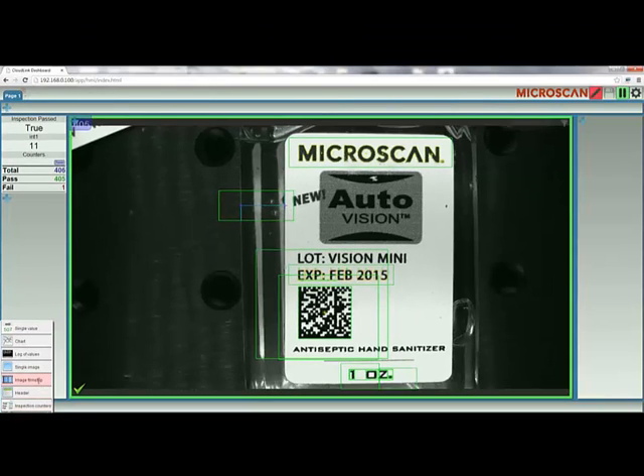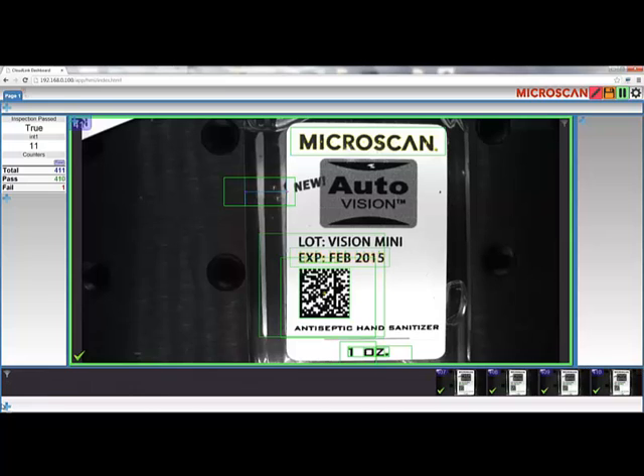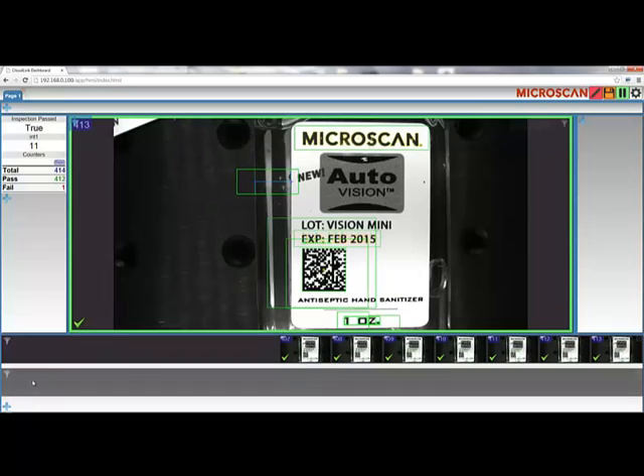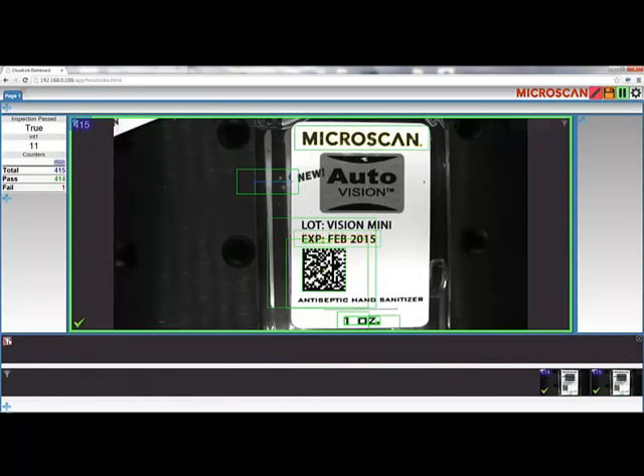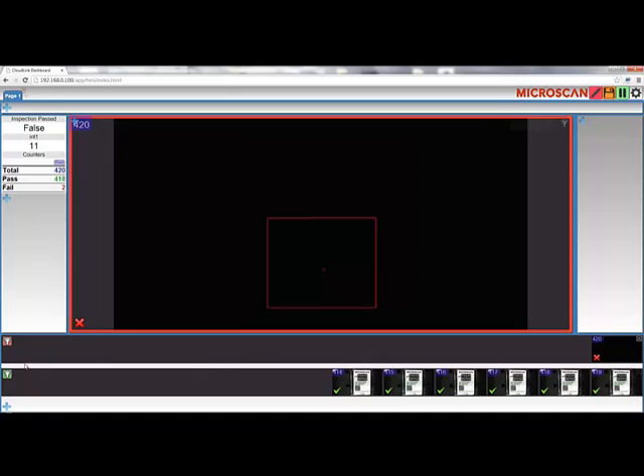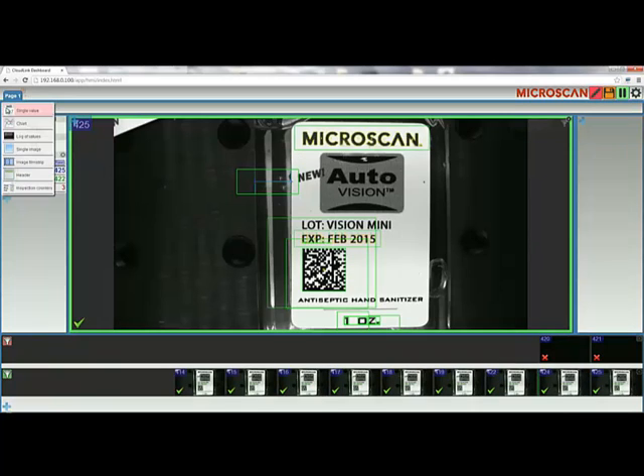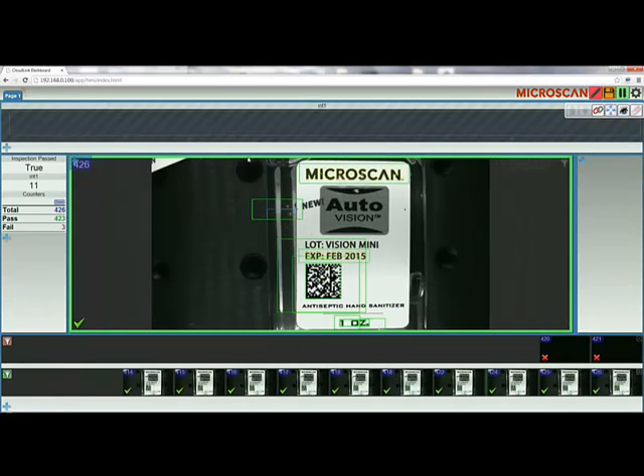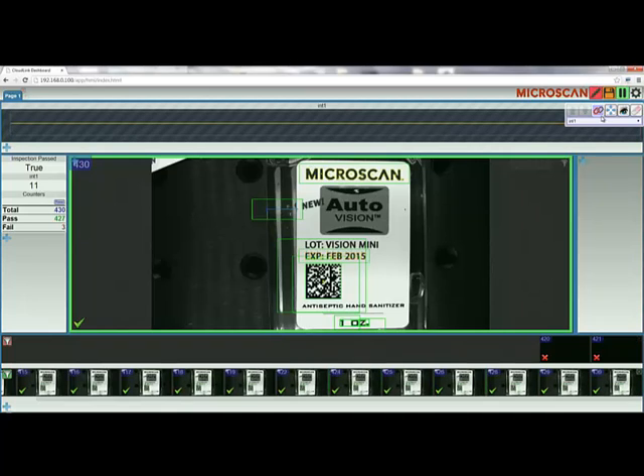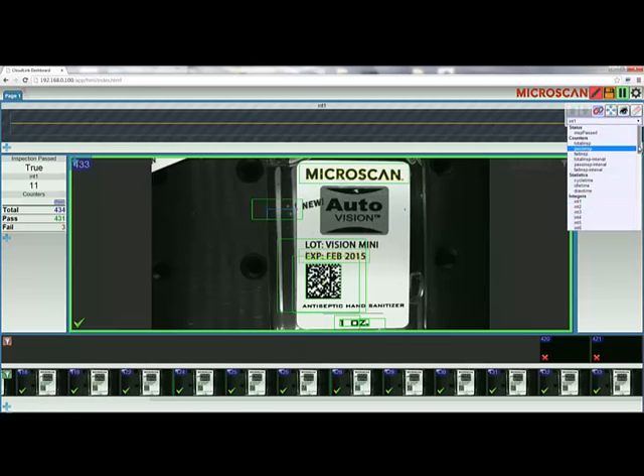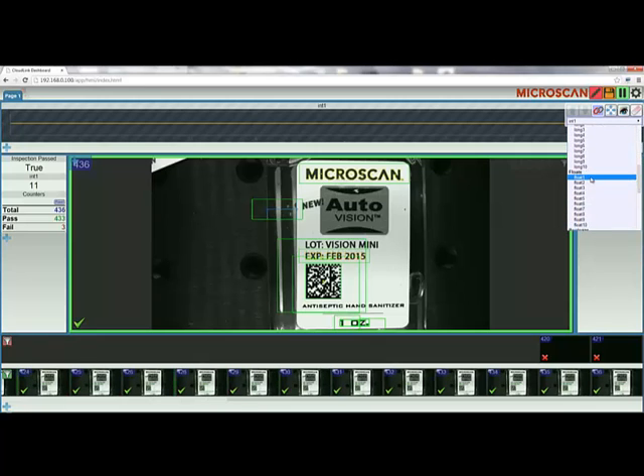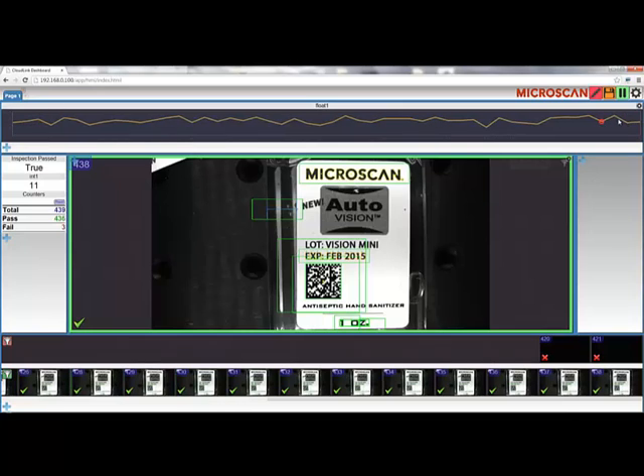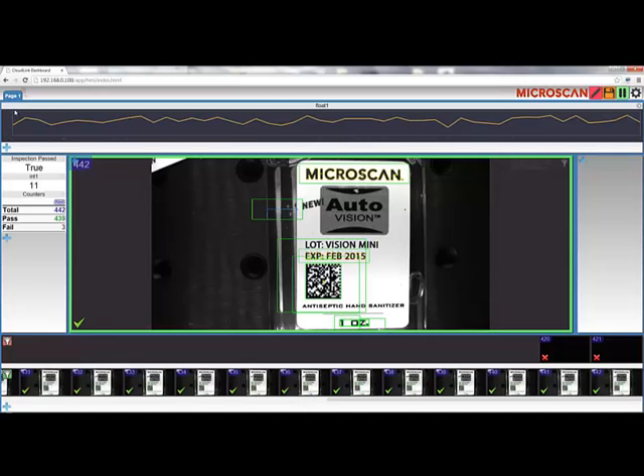I can insert an image filmstrip here at the bottom and show the image history. I can add a second one here as well. And set the first filmstrip to show me only the failed images, and the second to show me passed images. If I make an image fail, we can see it show up in the top filmstrip. I can also add, for example, a chart to the top here, which I can use to graph Microscan link values. In my inspection job, I've already linked the value for my label position measurement to float number one. So, if I choose float one for my chart, we can see the measurement values graphed here, ranging from 177.1 and 177.4 pixels.